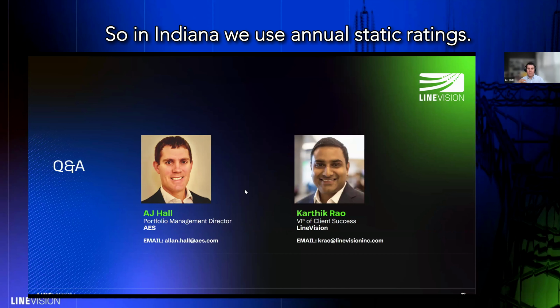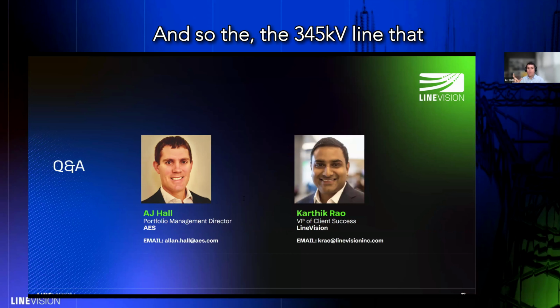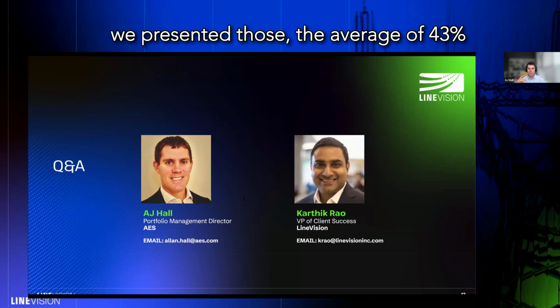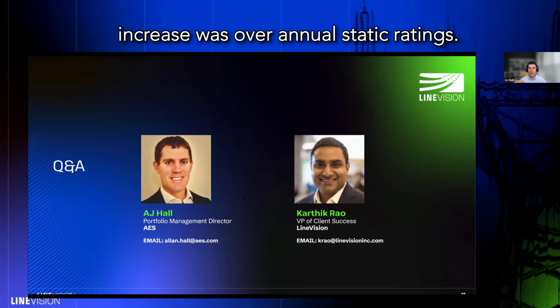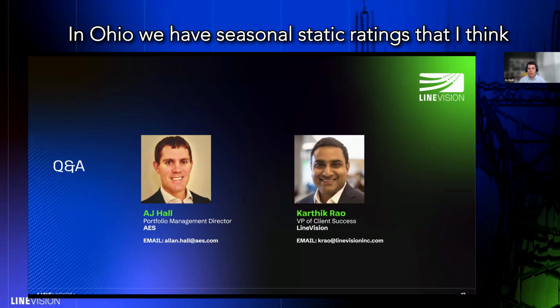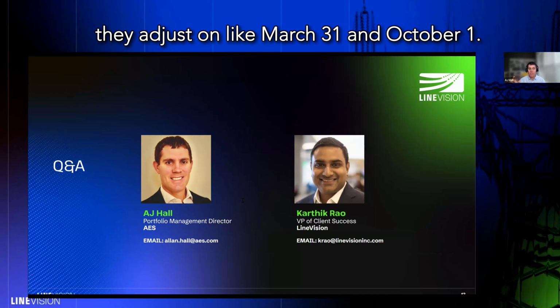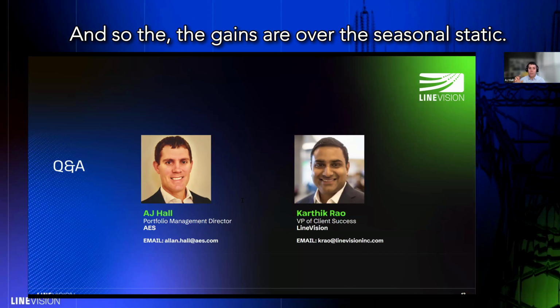In Indiana, we use annual static ratings, so the 345 kV line we presented, with an average 43% increase, was measured over annual static ratings. In Ohio, we have seasonal static ratings that adjust around March 31st and October 1st, so those gains are measured over the seasonal static ratings.